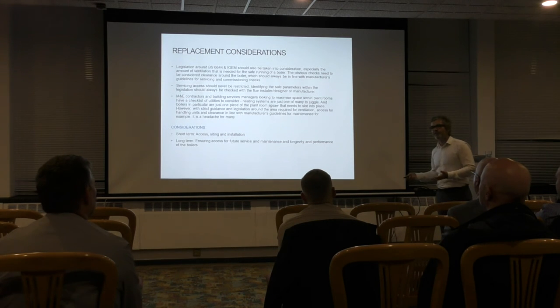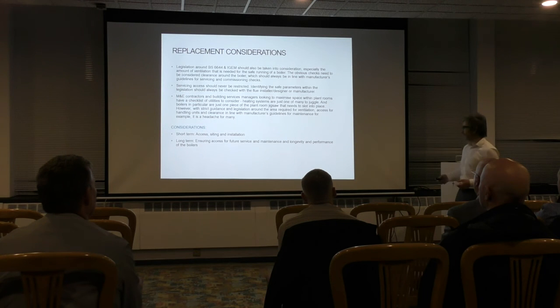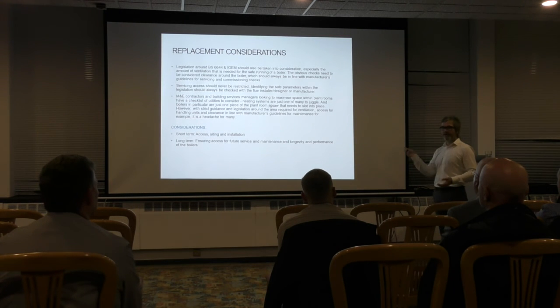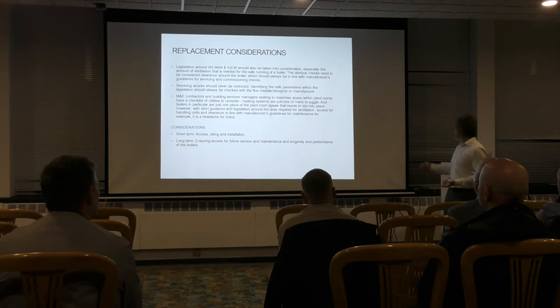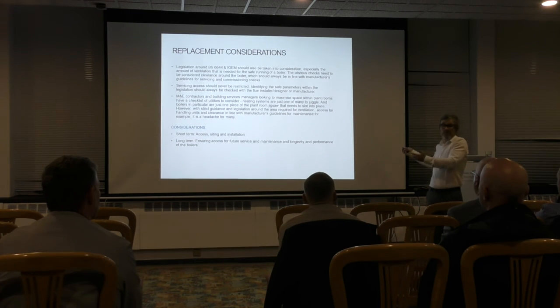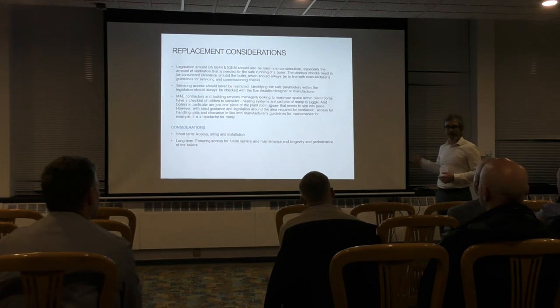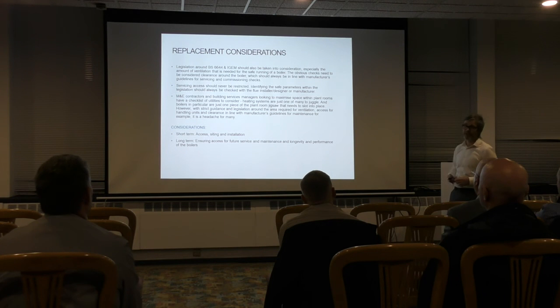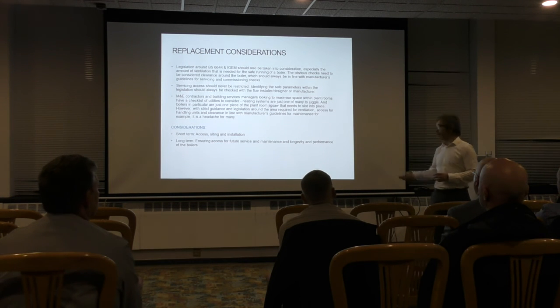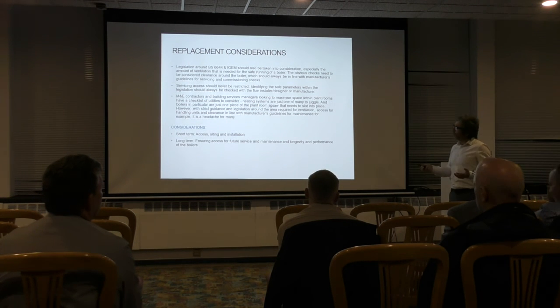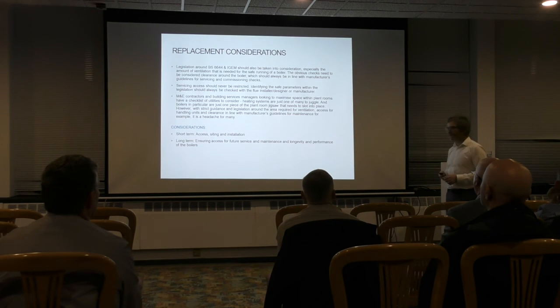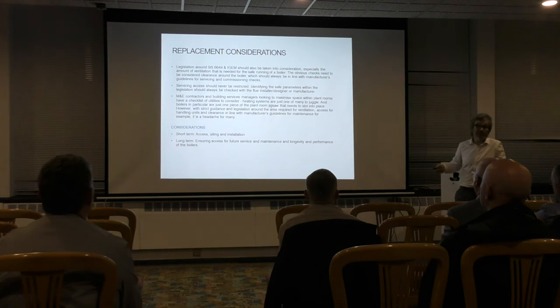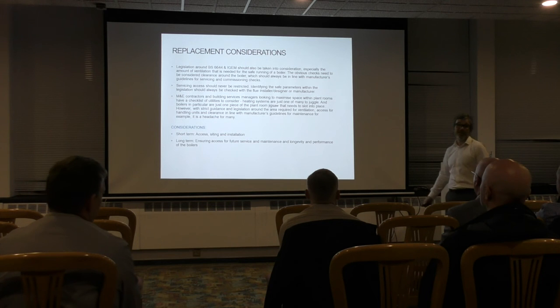But really, things like legislation and, for example, flues. I touched on flues earlier. It could be that you go to your site and you say, well, actually, I know they've been fluing out of that wall for the past 10 years, but we've now got a building opposite, which has got openable windows, for example. Actually, no, we can't flue out there anymore. We've got to take it up through the building or up through the wall. And your building occupier or owner may just think you're being a bit of a jobsworth. But it's so important that we meet it. As I said, if we don't, then the system just gets shut down.